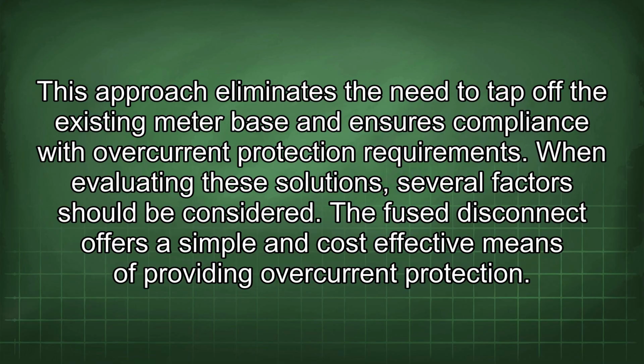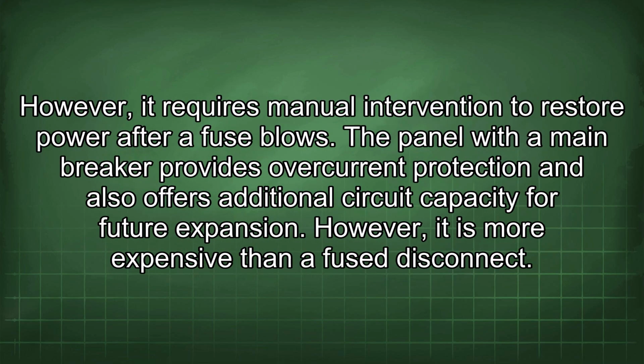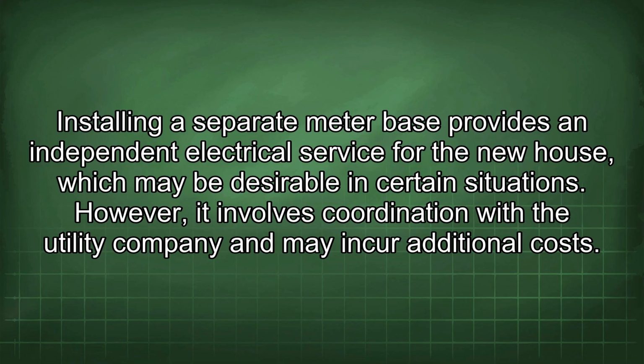The fuse disconnect offers a simple and cost-effective means of providing overcurrent protection. However, it requires manual intervention to restore power after a fuse blows. The panel with a main breaker provides overcurrent protection and also offers additional circuit capacity for future expansion. However, it is more expensive than a fuse disconnect. Installing a separate meter base provides an independent electrical service for the new house, which may be desirable in certain situations. However, it involves coordination with the utility company and may incur additional costs.